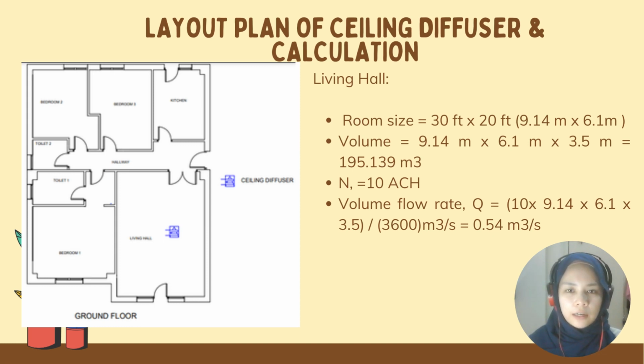For our living hall, room size is 30 feet times 20 feet. Our volume we got 195.139 meters cubed, and we got 10 ACH, and our volume flow rate Q we got 0.54 meters cubed per second.